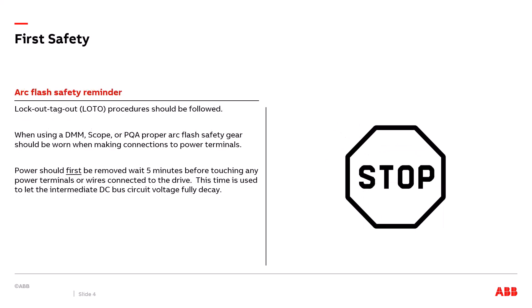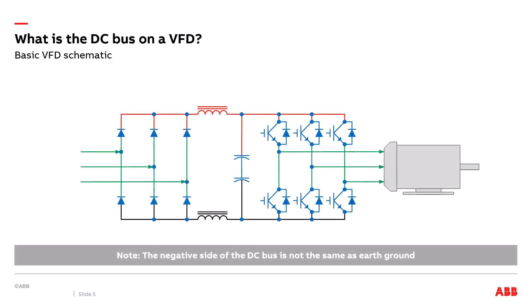Electrical safety is very important when working with a variable frequency drive, especially when making measurements on the DC bus of the drive. You should wait five minutes after power has been removed before making any connections of voltage probes to the VFD. For those that are not familiar with the VFD schematic and what it means to measure the DC bus of a drive, I just want to cover that real quick.